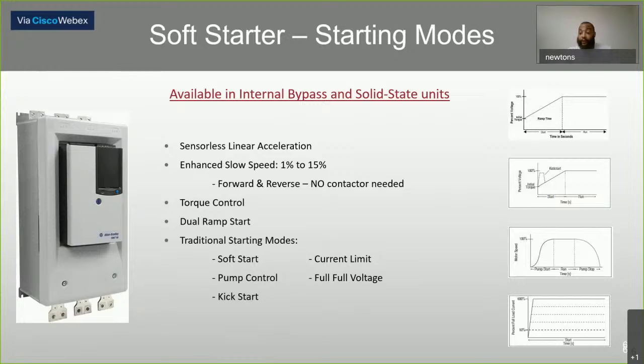Another good advantage of your soft start is that you can also put these on a network. You can put these on Ethernet, among other networks, but Ethernet is quickly becoming the standard in terms of network topology. Again, you can monitor your current, number of starts, and the energy that you've been using. If you have any warnings or trips, that information can be sent back to your PLC or your HMI, and you can get that diagnostic information to make preventative decisions to prevent downtime.